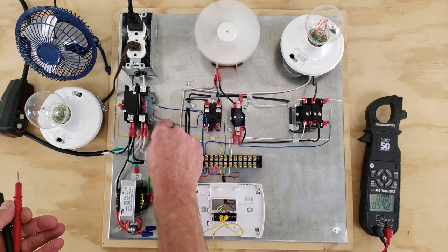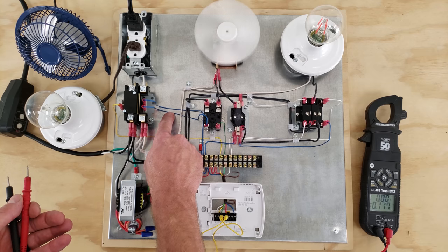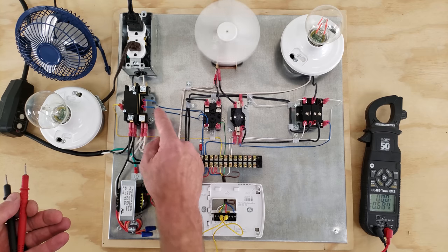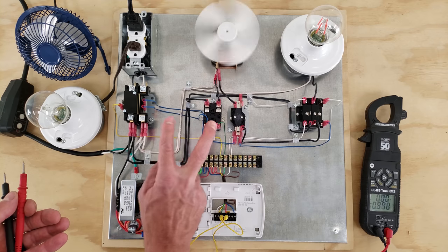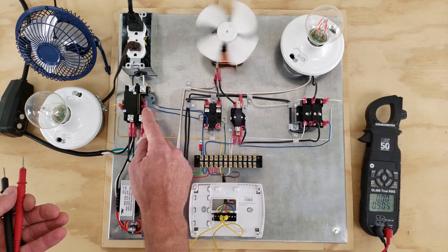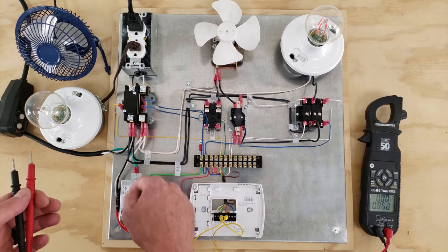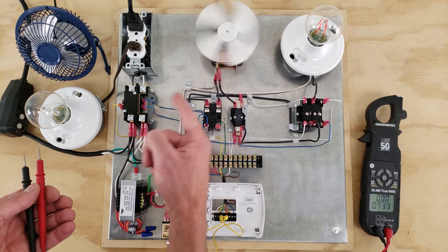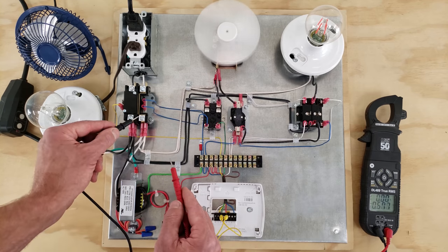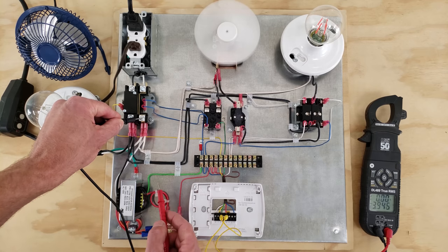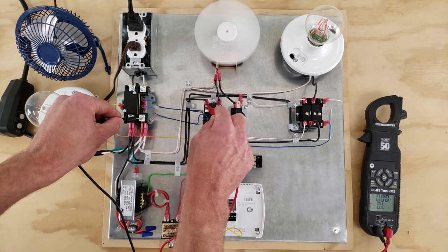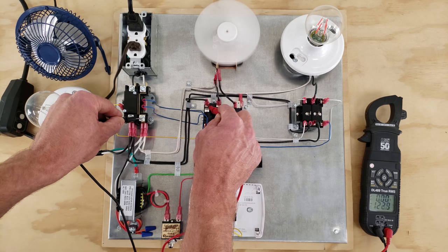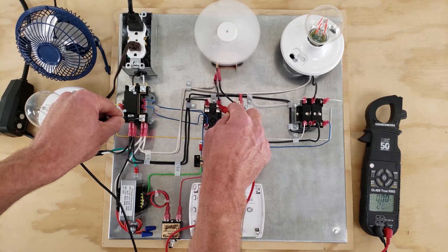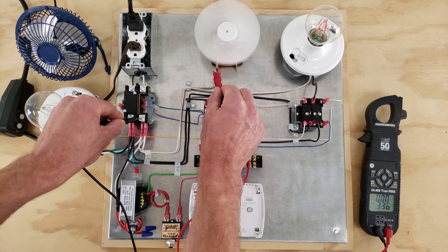So I don't know if you can hear that clicking or not. So that's a problem inside one of our crimp connectors. So we would go ahead and replace this wire or cut it and add on a new crimp connector. So we can see automatically right now we have our 120 volts through. And if we wanted to follow that, we could just put one tab on our common and we could put our other over here, 120, 120. And then obviously our fan's running.